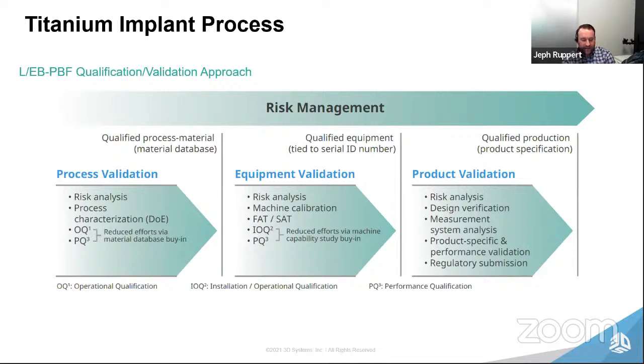And then from a product validation standpoint, at this point, the user would understand what the worst case is and then work towards that worst case product development. So this is typically where you look at the cleaning validation in powder systems. Obviously getting the powder out of there is always the trick. There's not great guidance from a regulatory standpoint on what this looks like, but then also the fit, form, and function of the device. So breaking it, making sure that the fatigue properties are what we need them to be. Different indications are going to require testing.